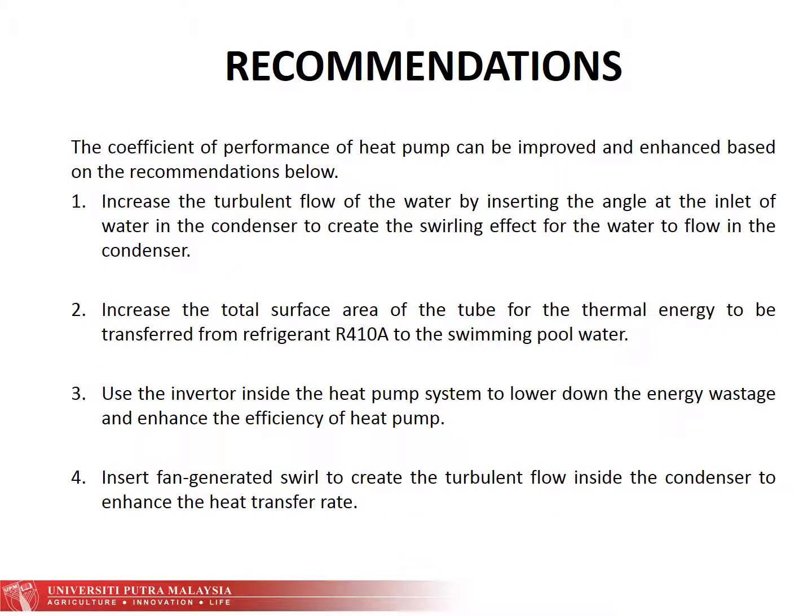The COP of the heat pump can be improved and enhanced based on the recommendations below. First, increase the turbulent flow of the water by inserting the angle at the inlet of the water in the condenser to create the swirling effect for the water to flow into the condenser.